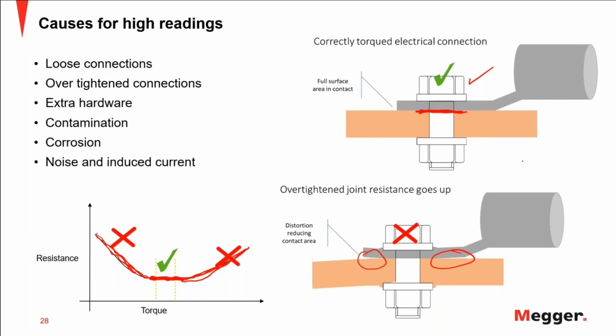And the other reason could be external. You could have noise or induced currents that affect your measurement. So once you get a result, and if it's out of what you're expecting, then you want to check all of these aspects. If you have the right torquing, if you don't have anything in between, or you have contamination, or if you are probably using a very low current, that could be affecting your result.